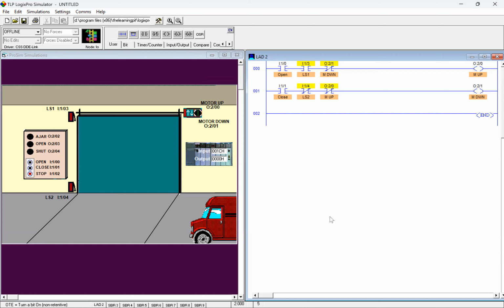Not only that, but you're going to come into this PLC and do it too. You just don't want those two to ever come in. So this one would be the normally closed contacts that you're wiring in from the auxiliary contacts on the starter. Not the overload ones, but the auxiliaries that are up on the contactor themselves.